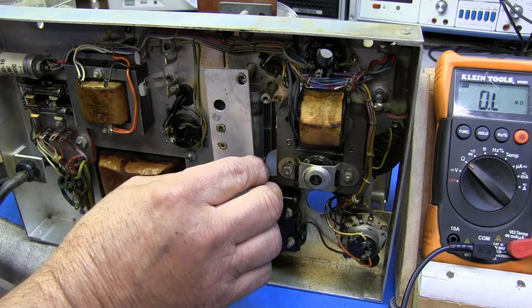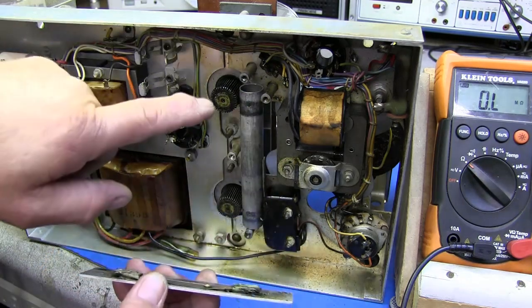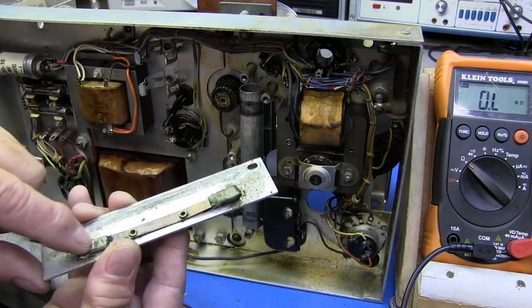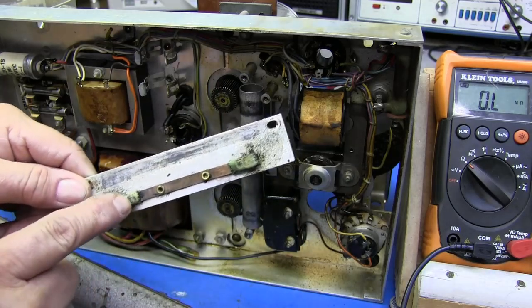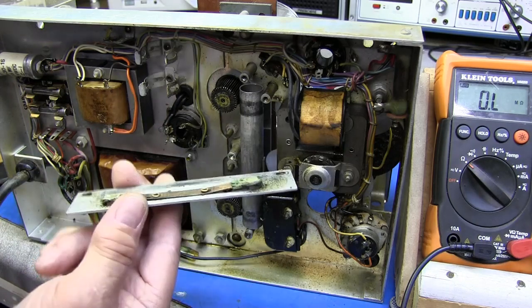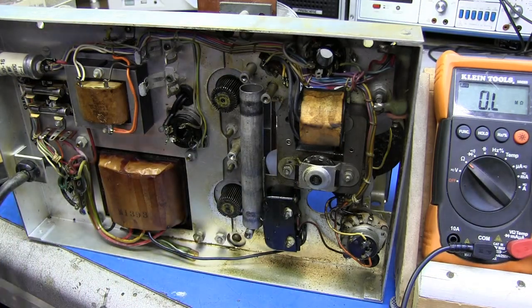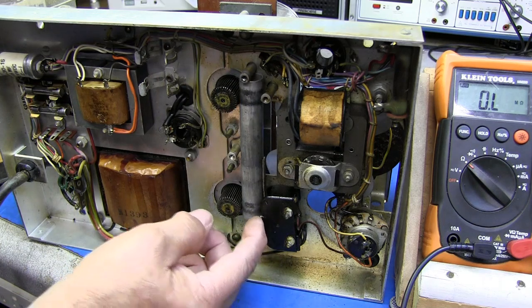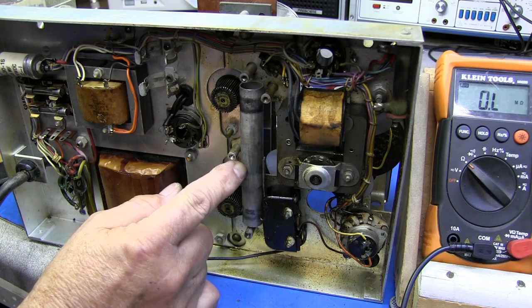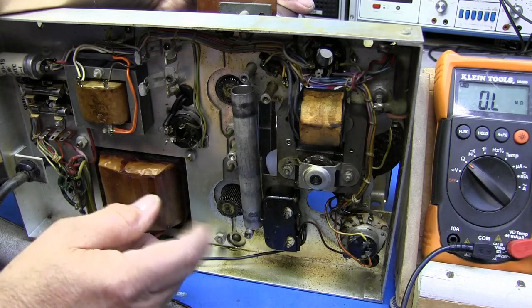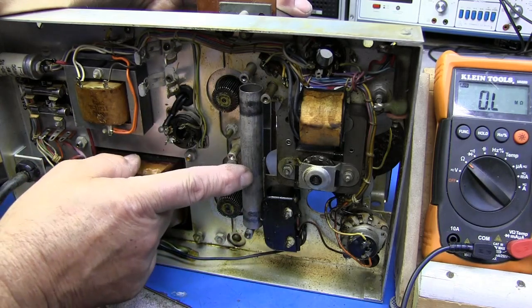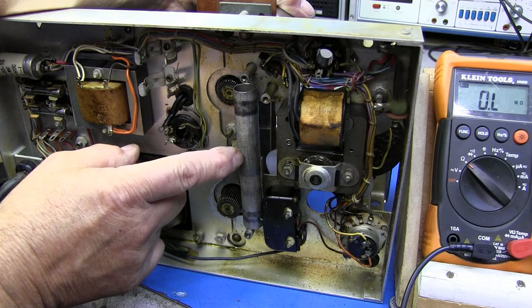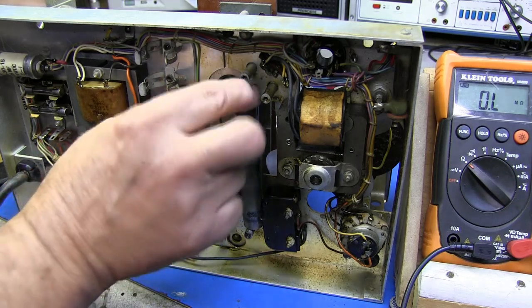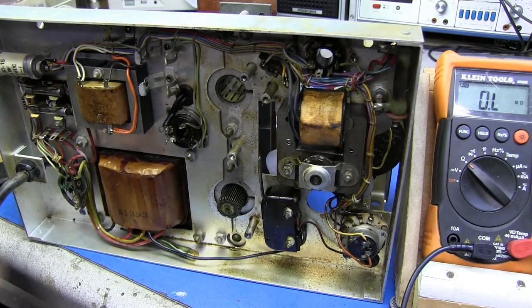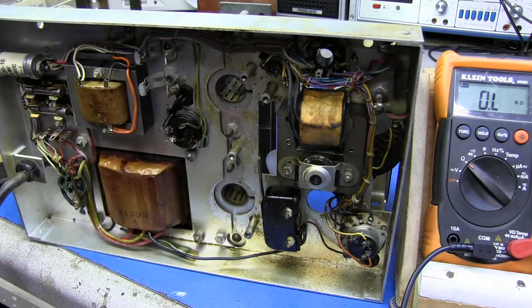When this plate is over it, that holds it all in place, and the bottom of these cups are grounded by these bars here that are also very dirty. If you notice, it's even got that green stuff on it. So all this I'll have to take out and put in my ultrasonic cleaner and clean them. I thought it'd be very interesting for you to see how this right here is designed. Very simple but yet effective. And when you take the cups out, you can hear the switch click. And that shuts it off. So a lot of cleaning to do to this thing.